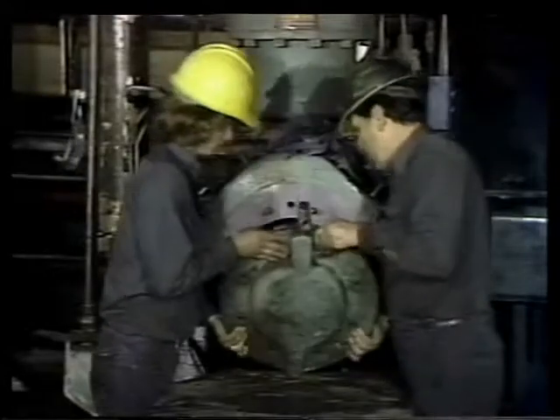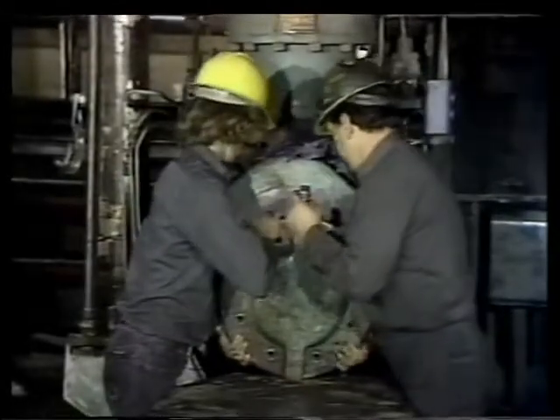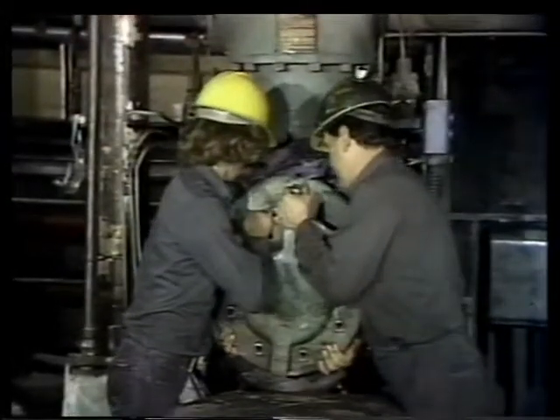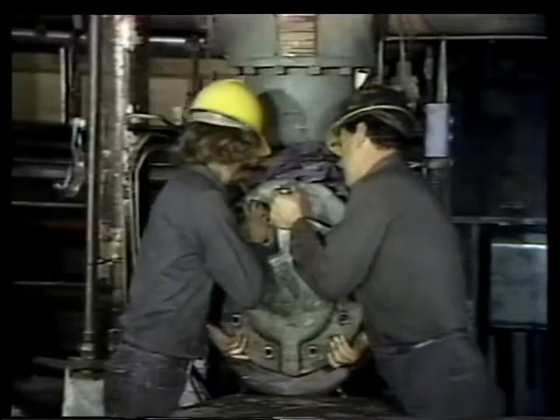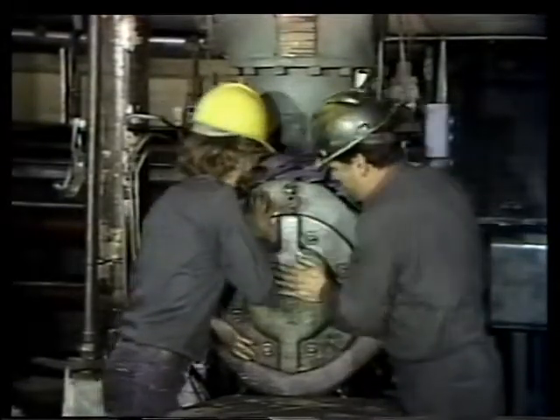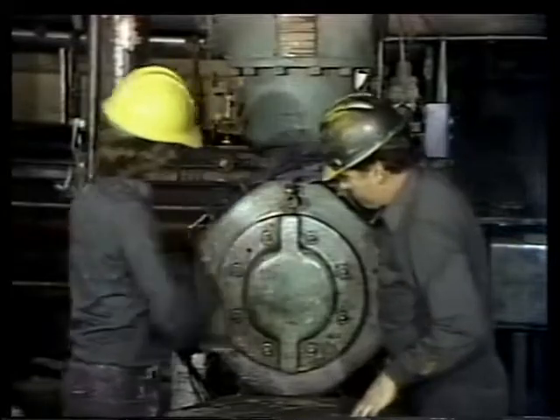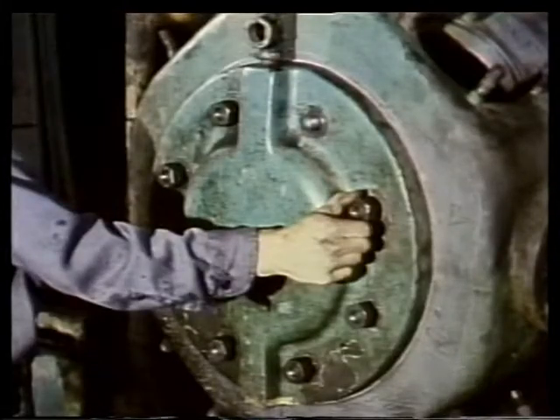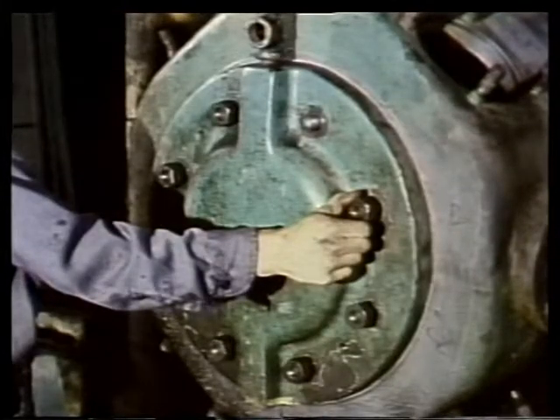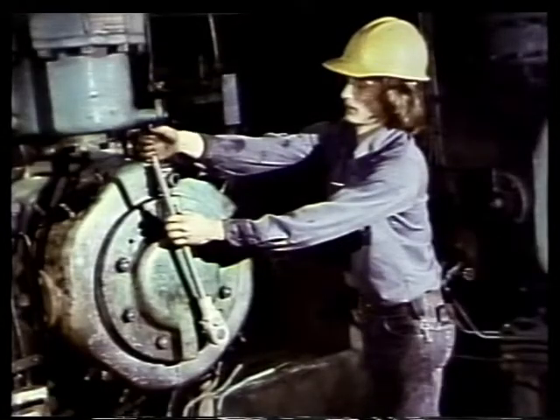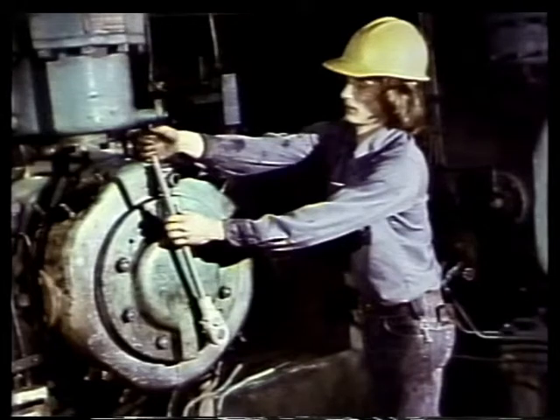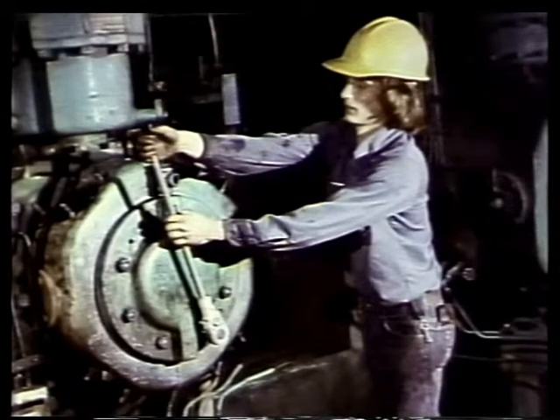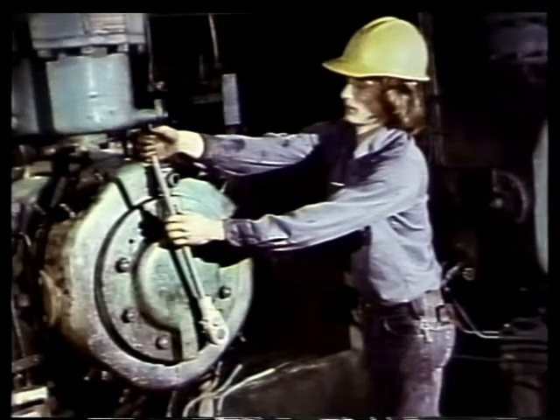It usually takes two people to lift the head up and place it on the cylinder. Put the nuts on the studs and tighten them securely with a wrench. Remember to tighten the nuts in an opposite pattern to ensure even contact between the head and the cylinder. The head is now secured in position.